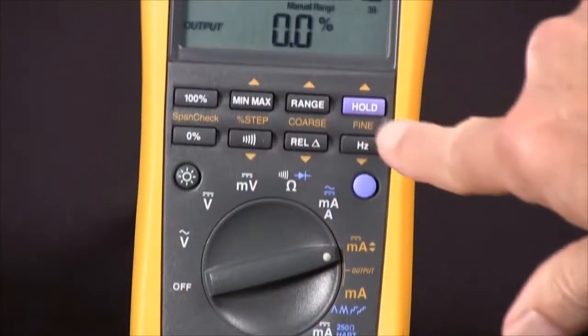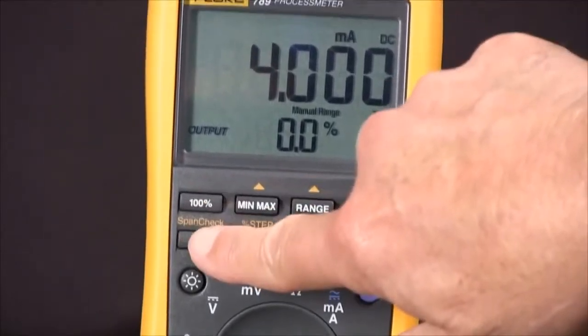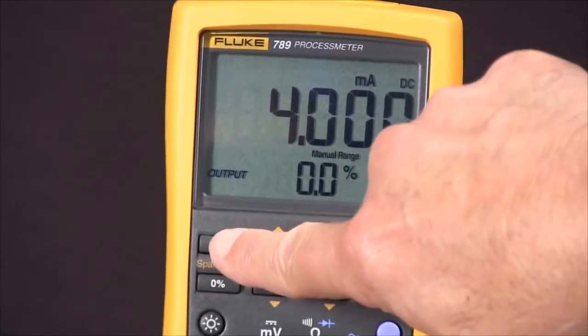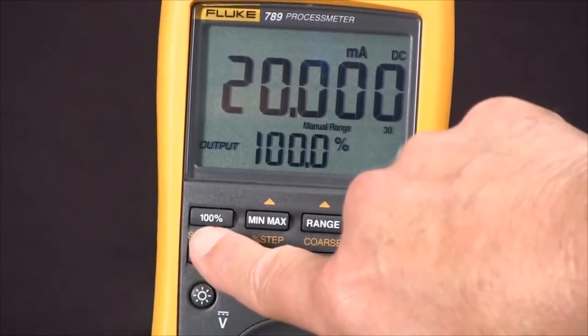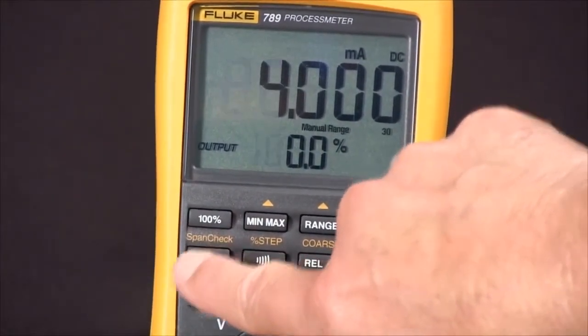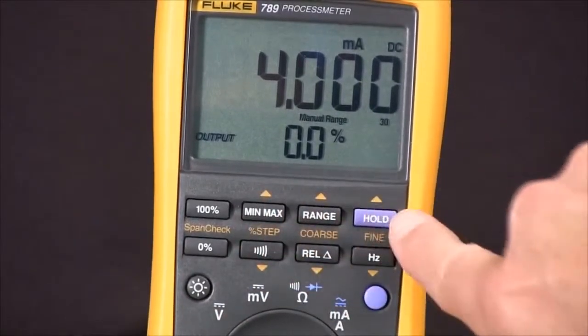We can start over here with the span check and we can go from 0% of span to 20 milliamps or 100% of span or zero. And then with these three we can do 25% of span coarse or fine adjustments.